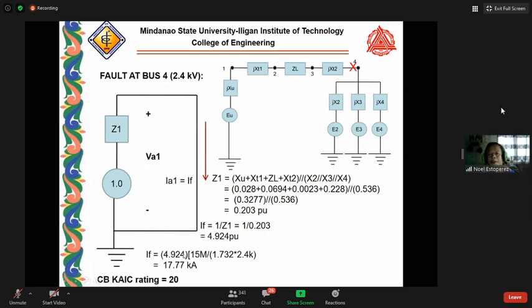The value of 4.924 will be multiplied by the base current. This is 15 MVA divided by 1.732 times 2.4 kV. So this gives us 17.8 kiloamperes downstream.